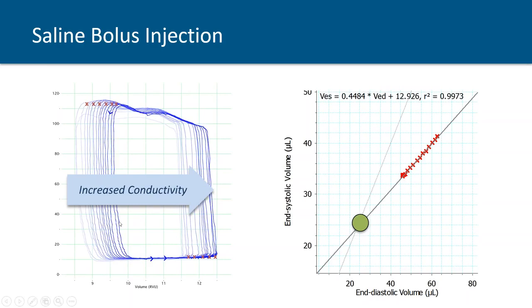What you see is the loops will shift rightward and they will get bigger at the same time. And what this technique essentially does is, if you look at the graph on the right panel, the dotted line is the line of identity, and the other line with the red crosses, or pluses, is taking the end diastolic volume and end systolic volume from each of those loops during the time that the saline is being washed in. And it regresses those loops until that line intersects the line of identity. And at that point, you're essentially saying that your end diastolic volume and your end systolic volumes are equal. So theoretically, or mathematically, you've rendered the blood non-conductive. So any signal you're getting delineated by that intersection point must be coming from outside the left ventricular blood pool.